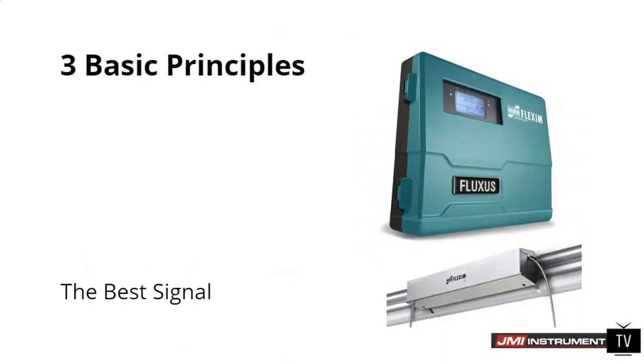For permanent installations, we'd like to see the SCNRs between 30 and 40 decibels. This allows for some leeway, such as some wet gas that comes by, a drop in pressure, things like that. You have some room that the meter has to drop signal and still maintain a measurement.